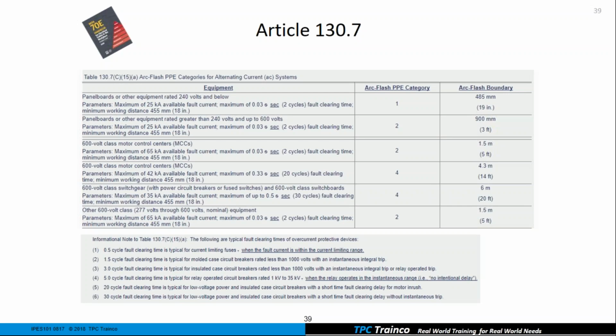And so the fault current cannot be over 25,000 amps, and our clearing time can't be more than 2 cycles. The fault current was always pretty easy to calculate. There's a lot of different ways we can do that. I have an app on my phone I can do it with. I've got software I can do it with. I've got a nice little tiny formula that we can actually even do longhand.